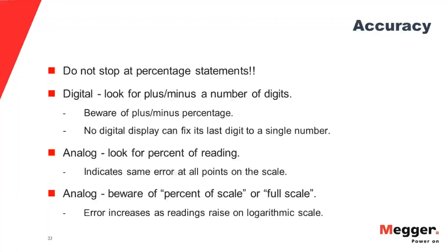And then the other thing to avoid is percentage of scale or something like that, because for units specified in that manner, the accuracy varies as you go across the scale, because the scales are typically logarithmic. So look for one that gives you the accuracy statement as percent of reading. In other words, it's the same accuracy at all points. So if you have a 2% accuracy, it's 2% at 1 megohm, and it's 2% at 1 gigohm or whatever. So those are the 2 things to look out for on accuracy statements.